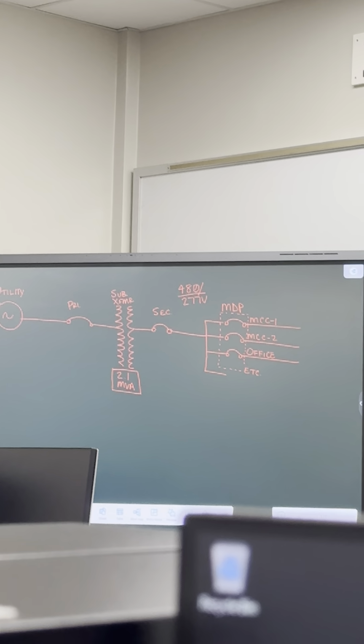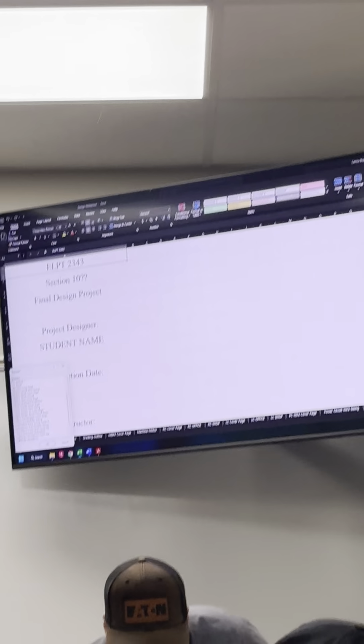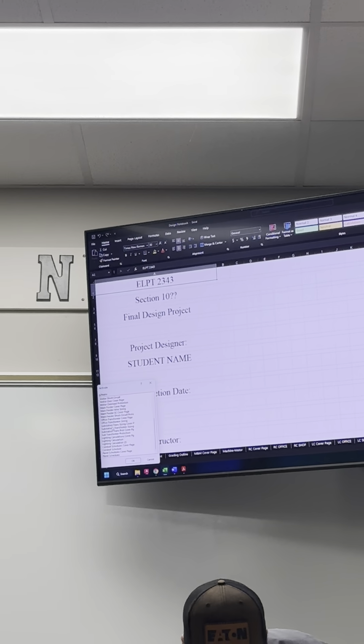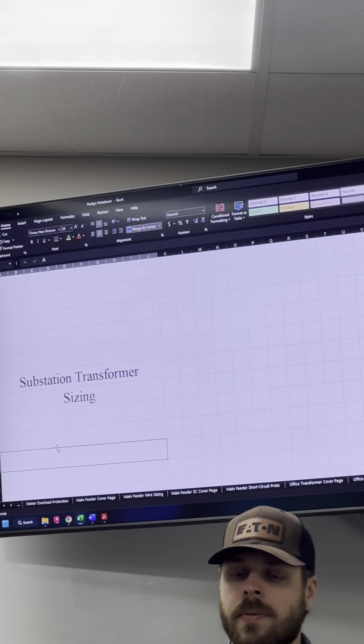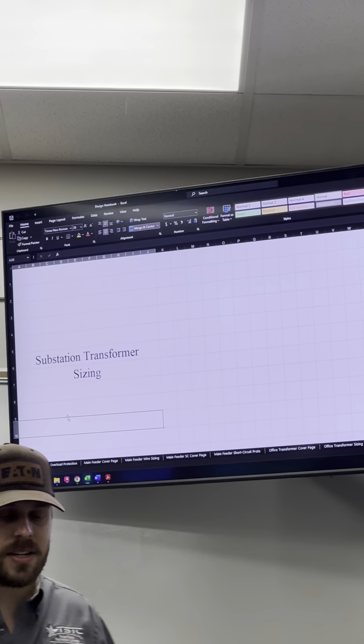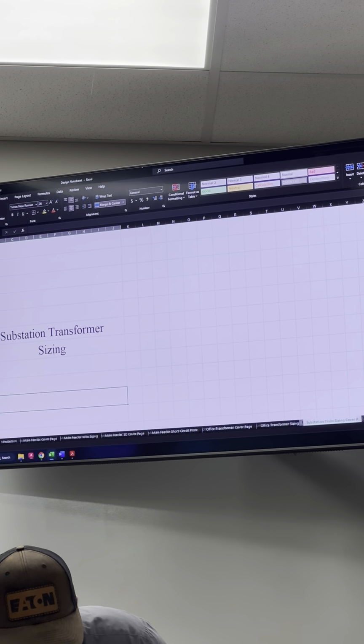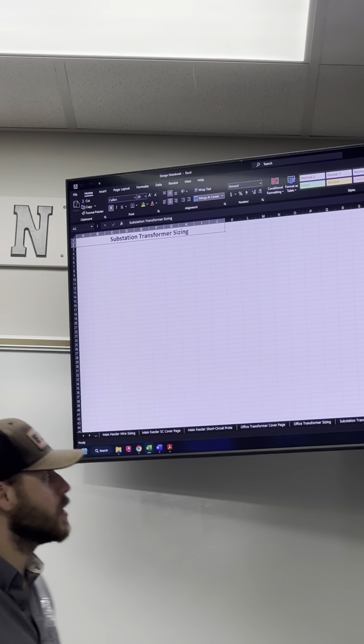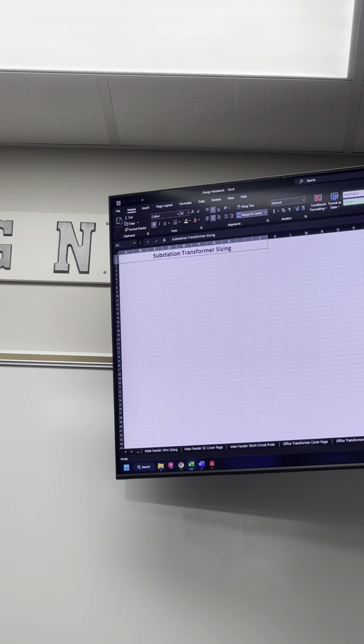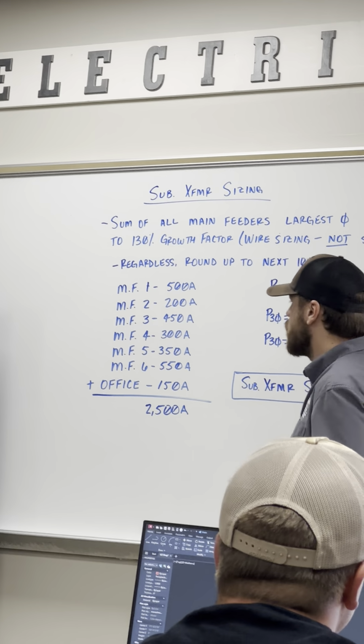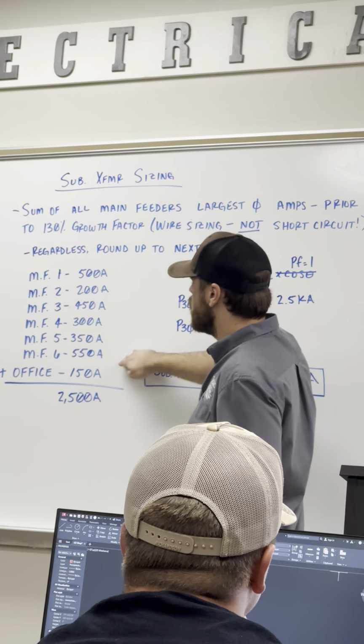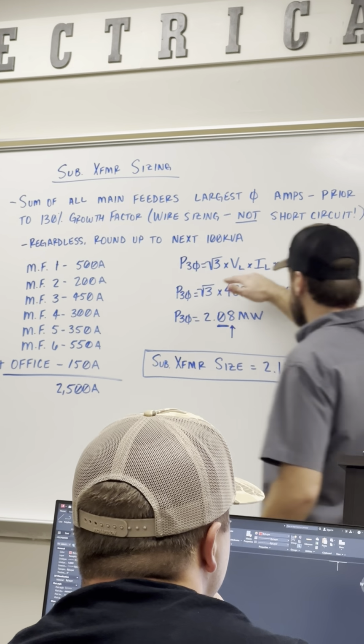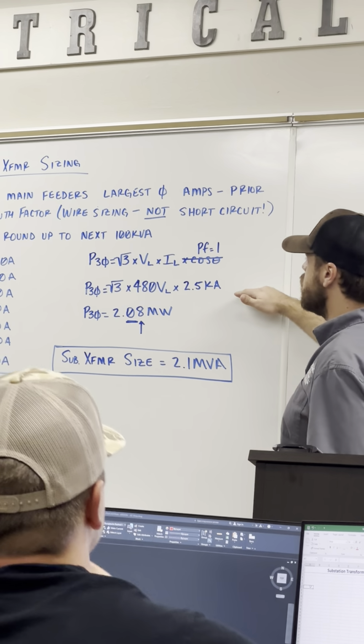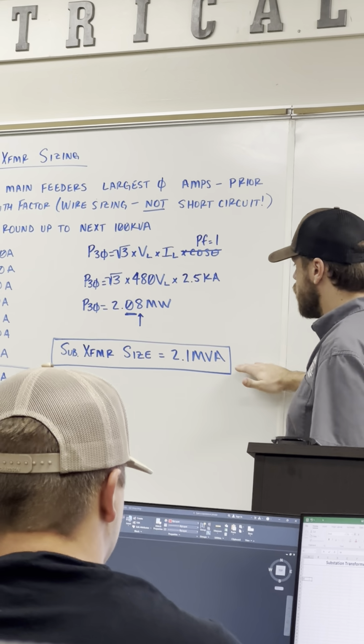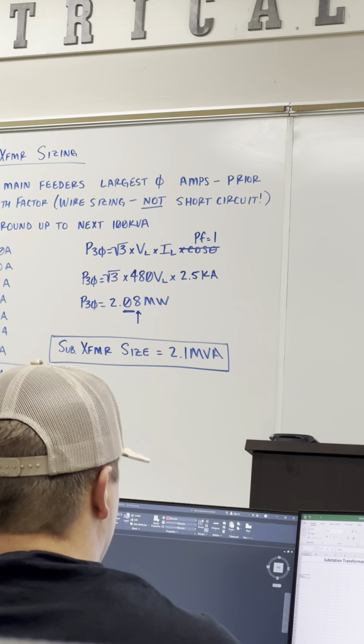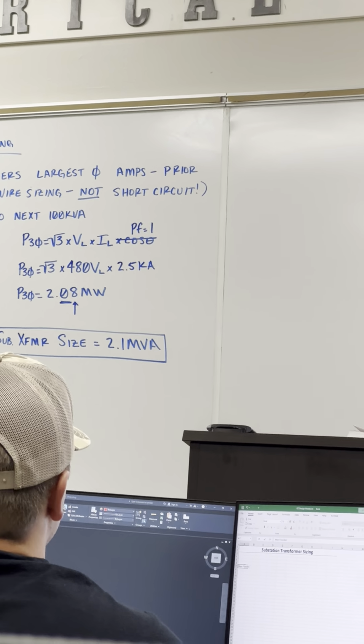So in our notebooks, if you go a little over halfway through the book, you'll see the cover page that says substation transformer sizing, and the page directly after that is titled the same but blank. On that blank page, you need to show all of this work: listing out all your main feeders, adding them up to get a total amperage, showing your three-phase equation, plugging your values in, what you calculated, and then what you're rounding up to pick your transformer size. Everything we just went through needs to be displayed on this page.